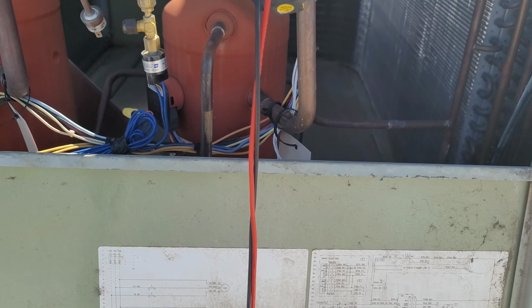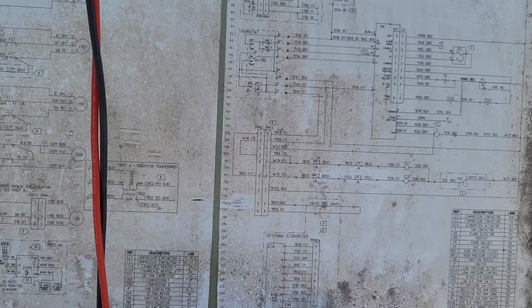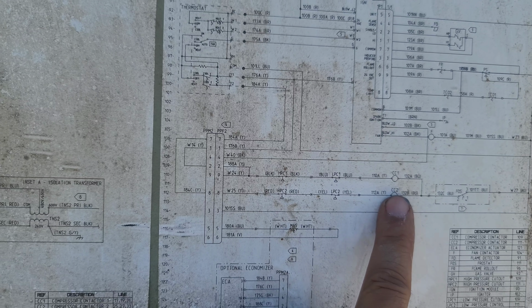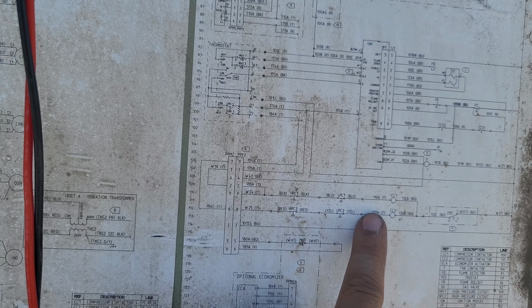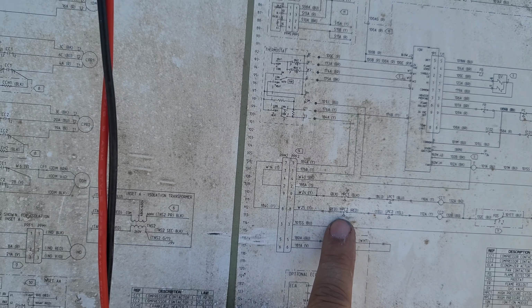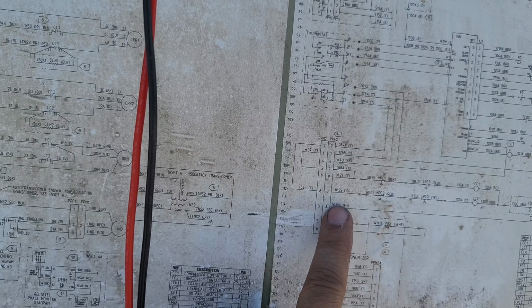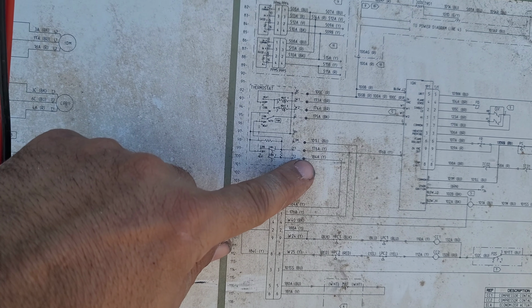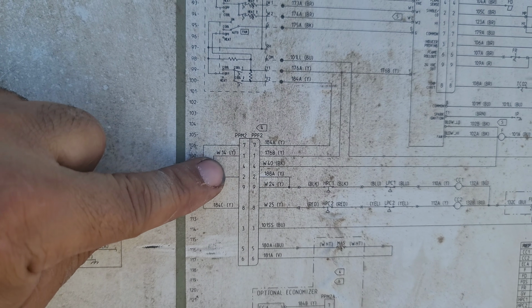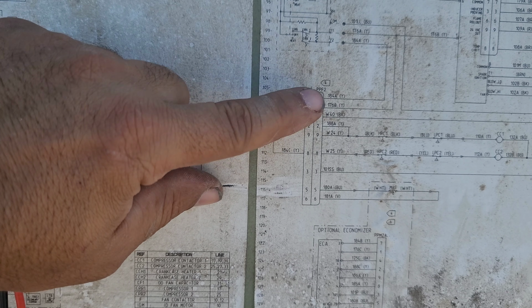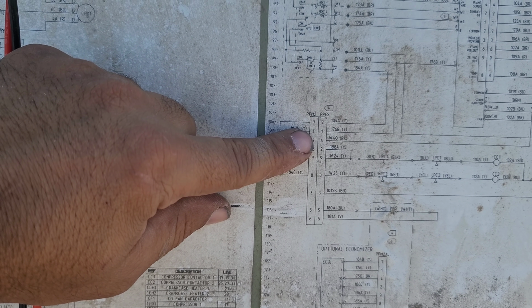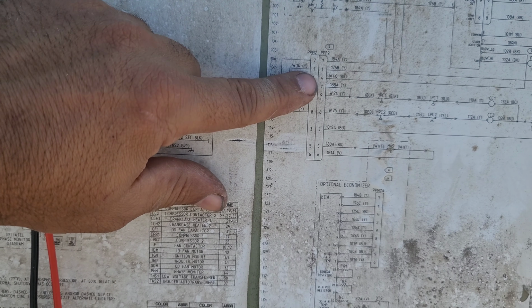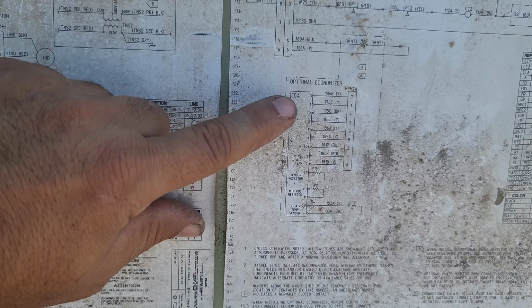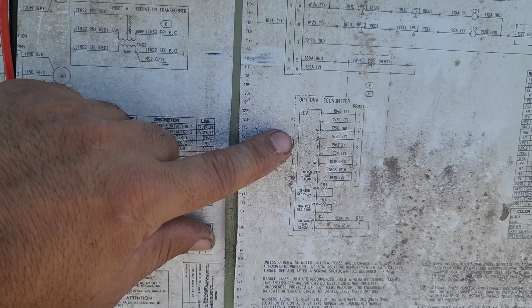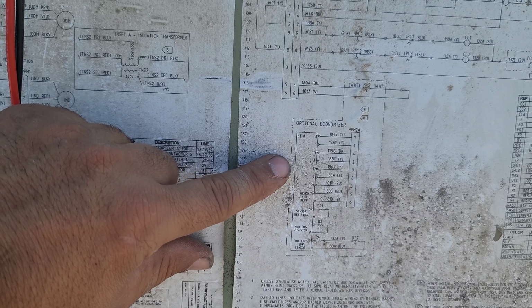So next thing we're gonna check. Okay, so we are okay between these two lines, Y1 and Y2, all the safeties are closed. And next thing, if we see here, the thermostat wire is going to this jack or plug here. So we have to find out where this is located, and we have an economizer in this unit, so we have to check the economizer board here. So what is going on with the economizer board?